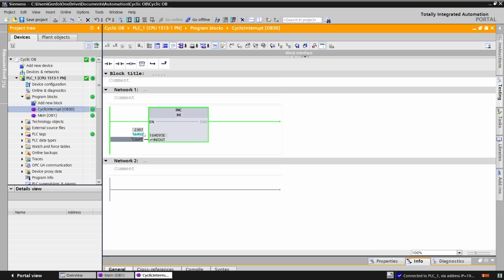So for some very special types of function blocks that you may find in different advanced libraries, such as creating ramps, or the most popular one actually, the PID loops, PIDs need to be implemented in this particular cyclic interrupt, and typically they run on a cycle time of 100 milliseconds. Okay, I hope this video helped you to understand and practice with cyclic interrupts or cyclic blocks.